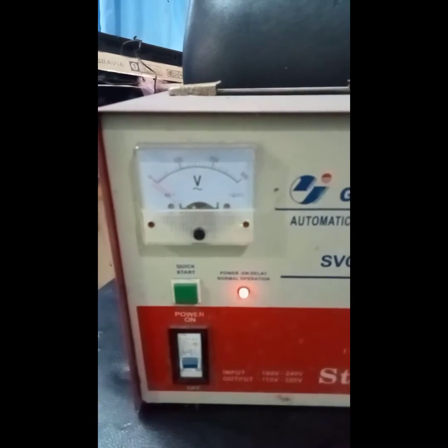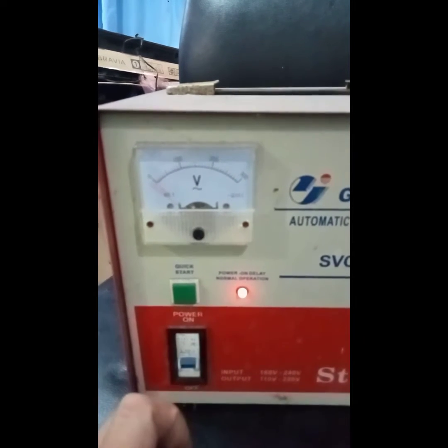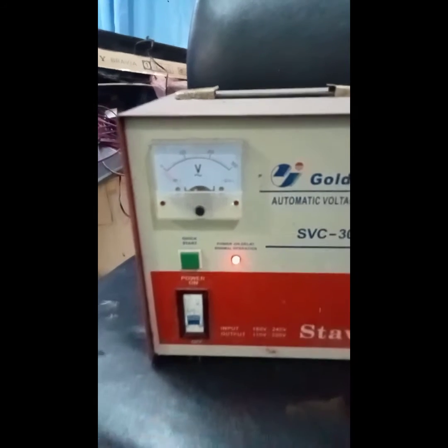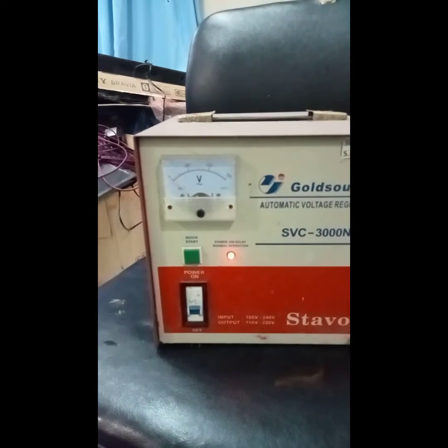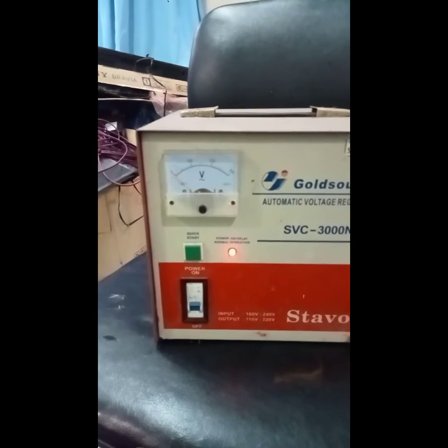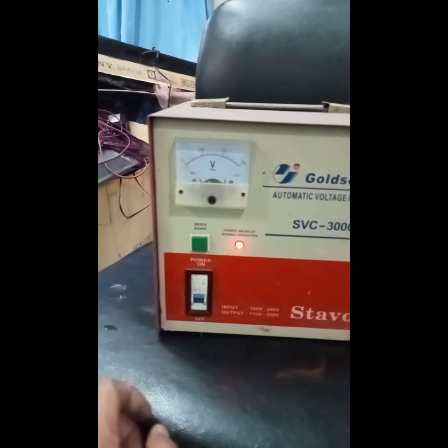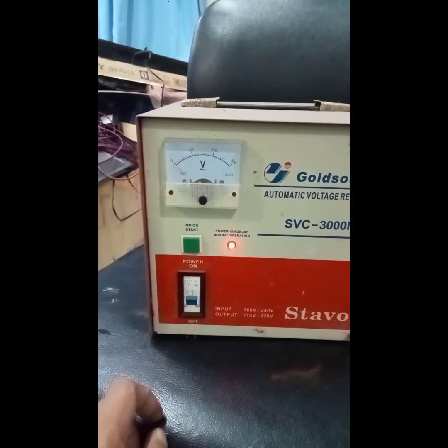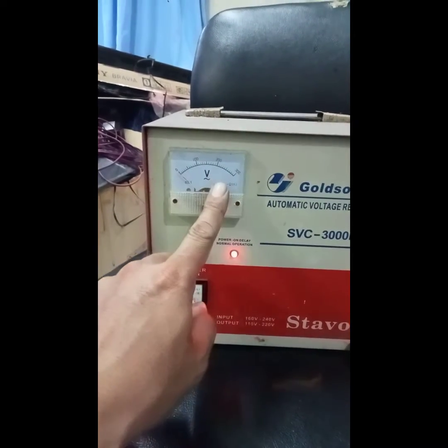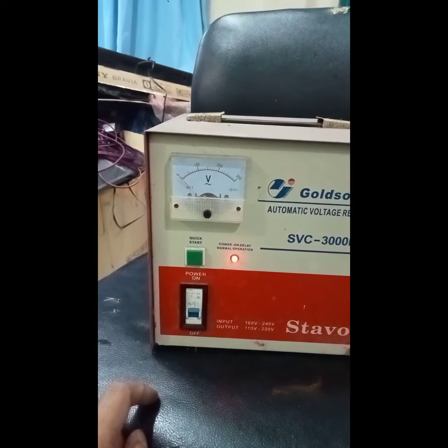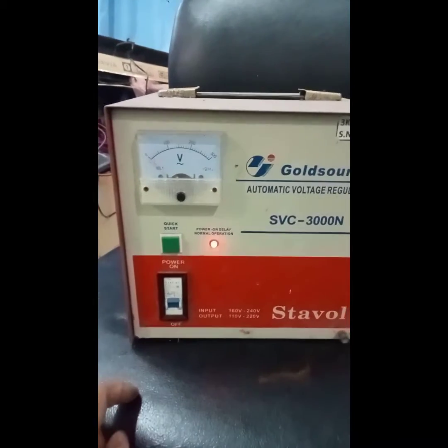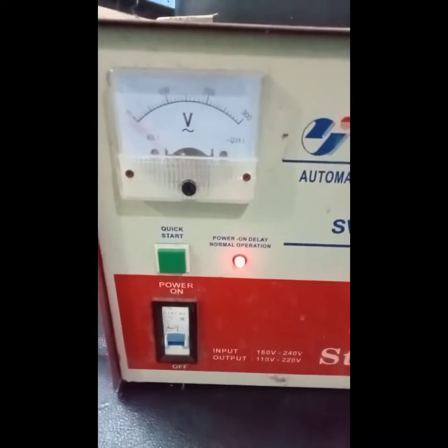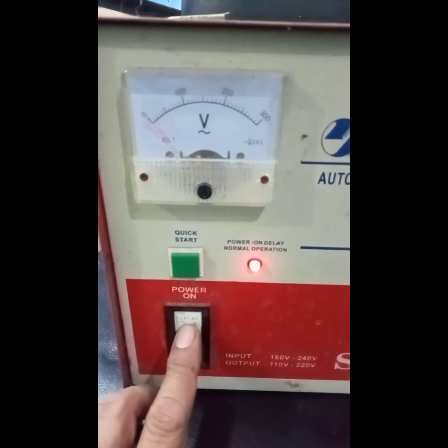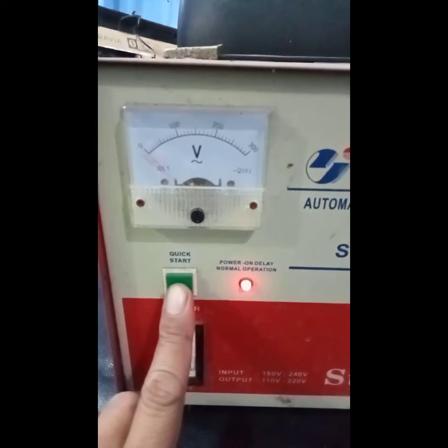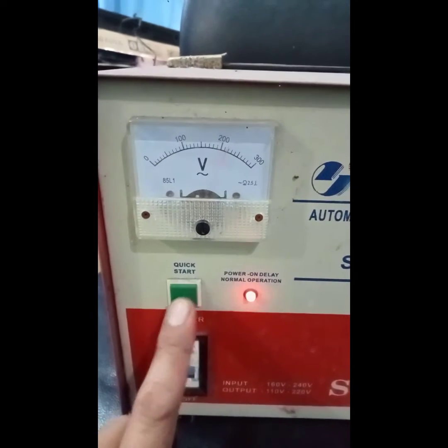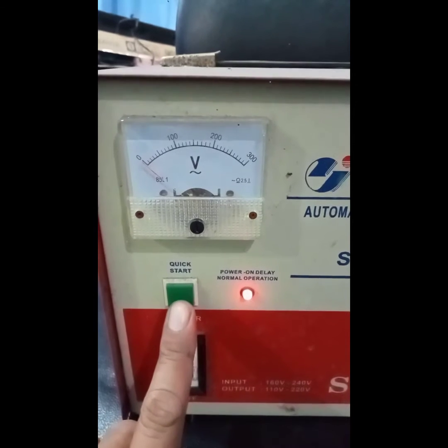So meaning there's a problem with our control inside. But if you wait this for at least 30 seconds or to 3 minutes, I think it would start, and this needle should stay at the 220 volts. So we're not going to wait for this one to turn on. So better fix the control inside so that every time you touch the quick start, it should hold the power, or meaning the voltage.